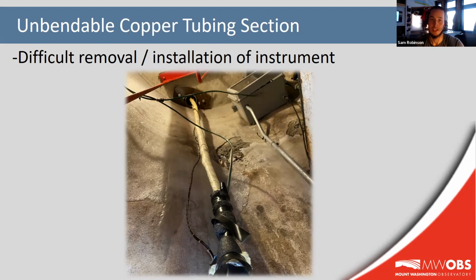It's also crucial during removal or installation that this section of copper tubing cannot be bent. This just means that extra care must be taken when the instrument is being removed or installed for maintenance or repairs, which then requires optimal weather conditions, many sets of hands, and very cautious movements. At the home of the world's worst weather, optimal weather conditions are a very rare occurrence. And even when they do occur, the availability of people to help, plus fitting everybody at the top of our instrument tower, is not an easy feat to coordinate.